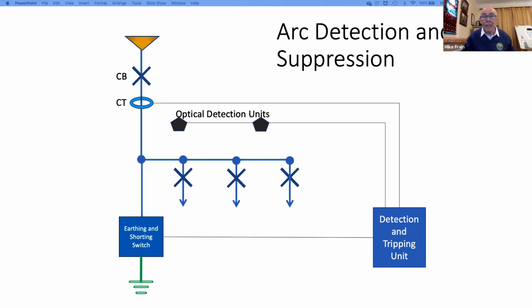As you can see from the diagram, they consist of a CT and optical detection units as well. It picks up the arc development. So simultaneously, when the arc detection units pick up ultraviolet light from the arc at that point, at the same time the CT picks up the rise in incident energy, the rising current.